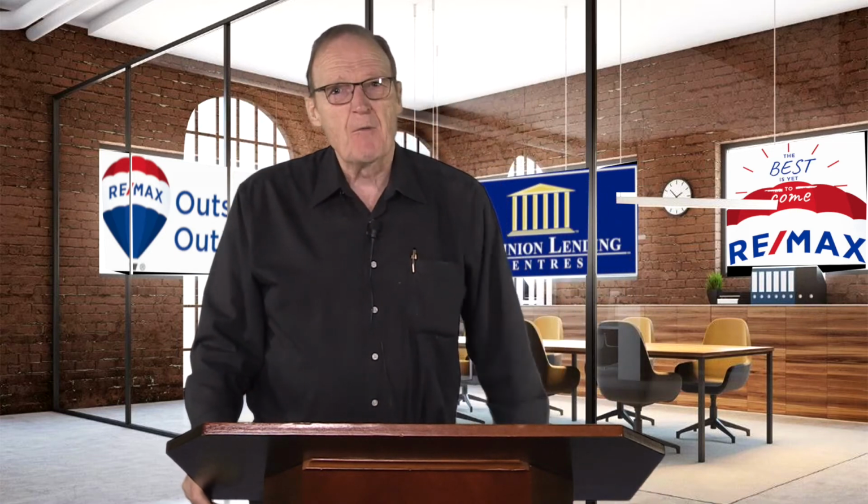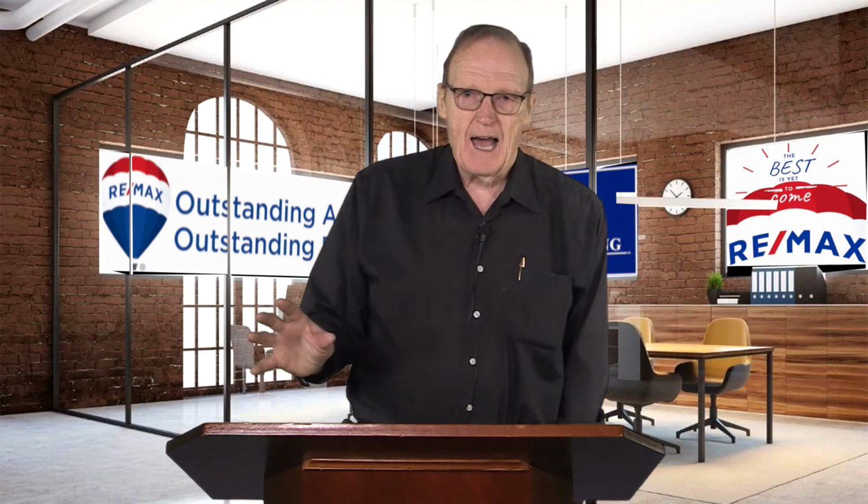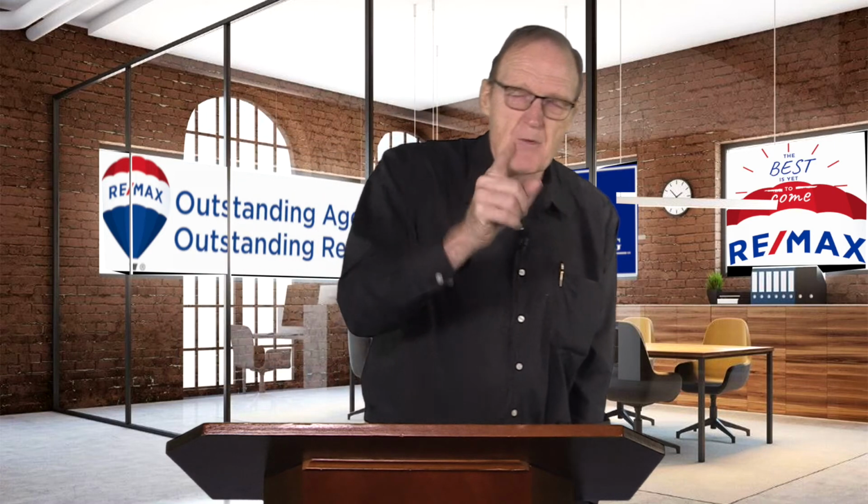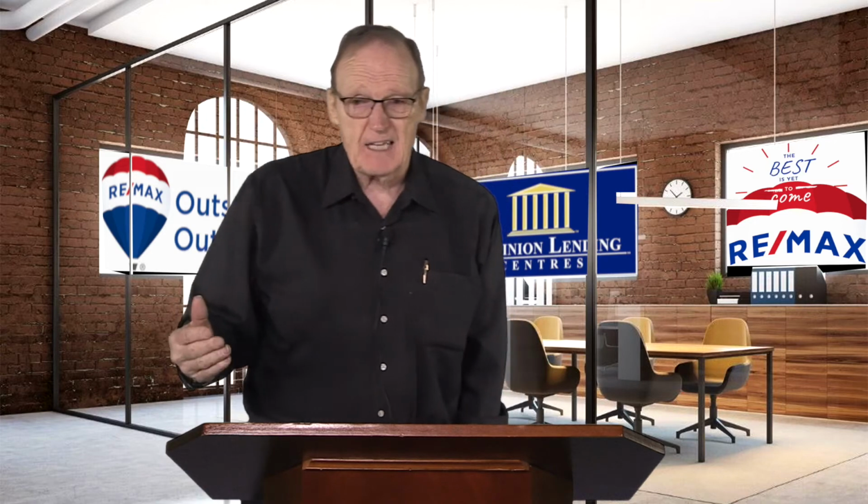All right, the third thing we want to look at is fire and smoke detectors, or at least also carbon monoxide detectors. This is really critical, again, when you have 2 or 3 units in a building that exit into a common hallway or stairway. Those common areas, the hallway and the stairway, must have direct wire interconnected smoke detectors. Now, it's not necessary to have direct wired smoke detectors in the units. Battery operated is okay. But in the common areas, like stairways and hallways, they must be direct wired. So you as a realtor look in and see whether those smoke detectors, first of all, are there, and secondly, whether or not they're direct wired.